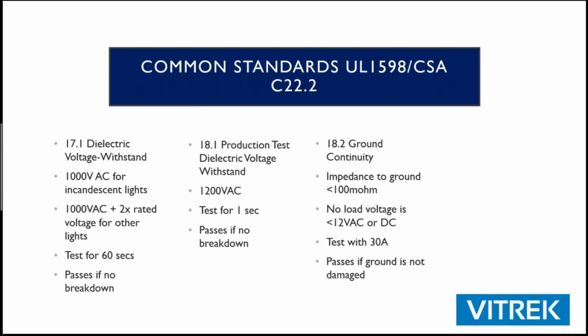All right, so this is a luminaire standard here. Voltages can be a little bit higher for luminaires. These tend to be class 1, where you're going to be also doing a ground bond test, certainly in production and type testing for production, sometimes only a ground continuity, depending on your power levels.